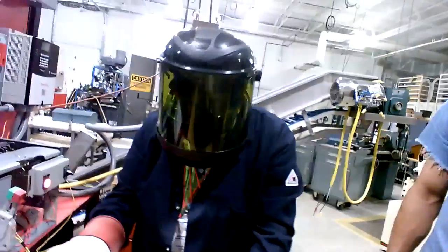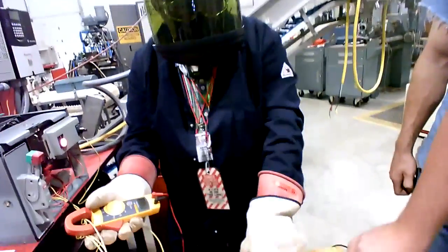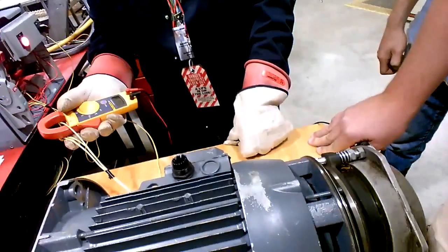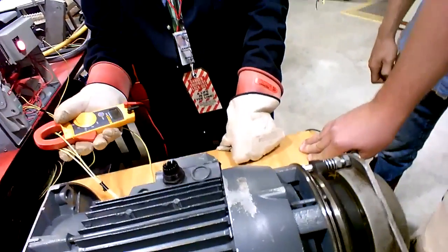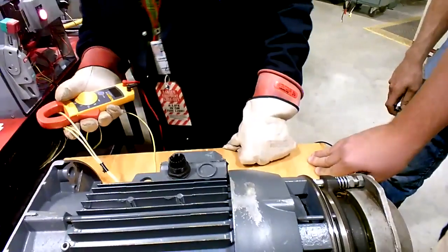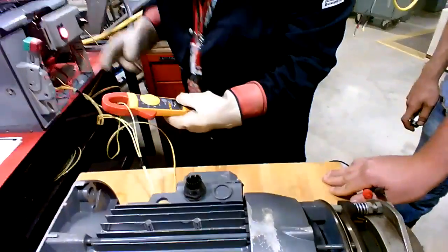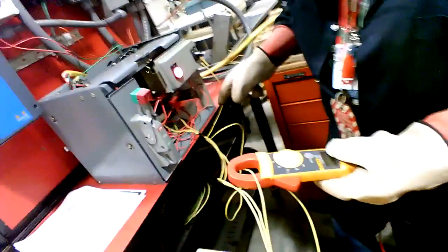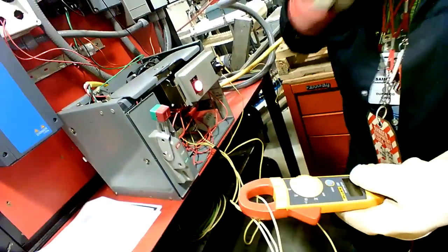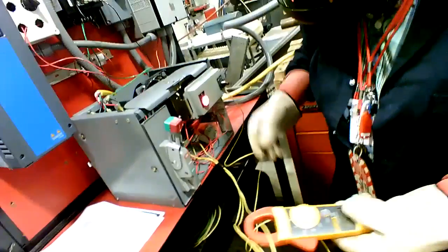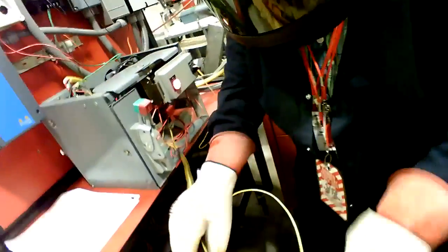When you're doing maintenance, checking motor current, those three should be similar. If there's an extreme difference in one of the legs on current, then you want to back up and check the voltage of each leg to ground. So let's say, for instance, to give you an example, we're going to cut this off.